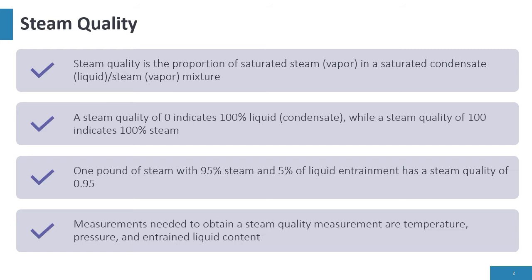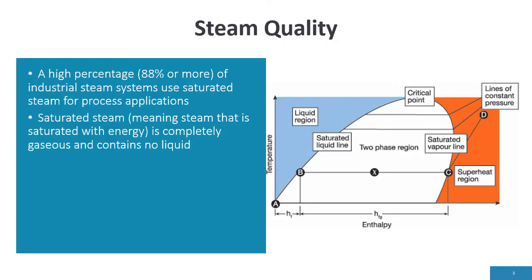One pound of steam with 95% vapor and 5% liquid entrainment has a steam quality of 95%, or 0.95. Measurements needed are temperature, pressure, and entrained liquid content. We'll talk more about testing methods in this presentation. A high percentage — 88% or more — of industrial systems use saturated steam for process applications. Saturated steam means steam that is saturated with energy, completely gaseous, containing no liquid. We have a tendency to think it means saturated with water or condensate — it does not. It is saturated with energy.